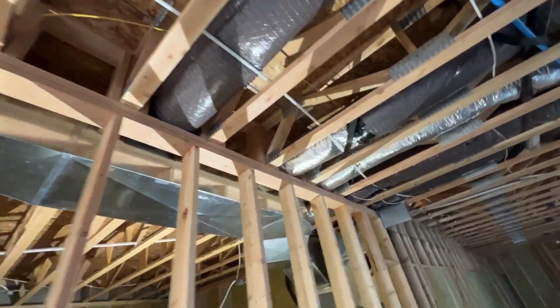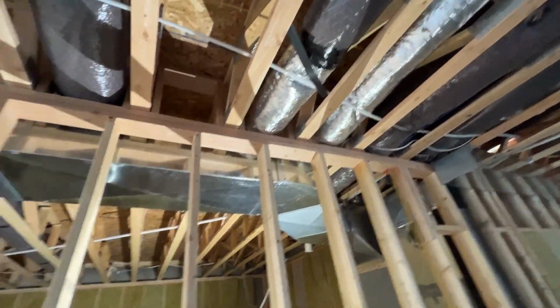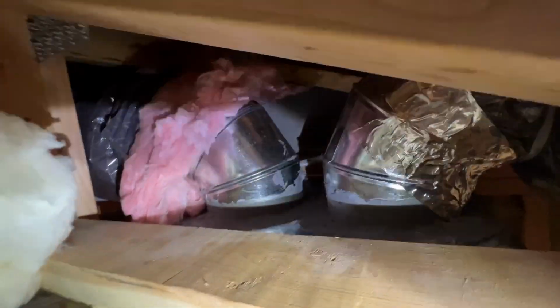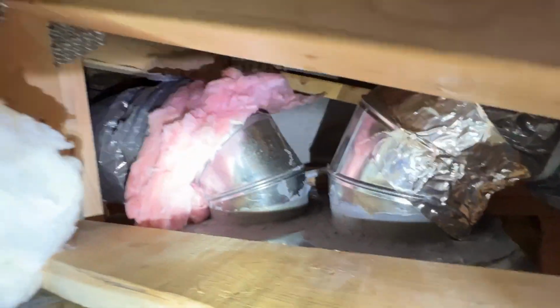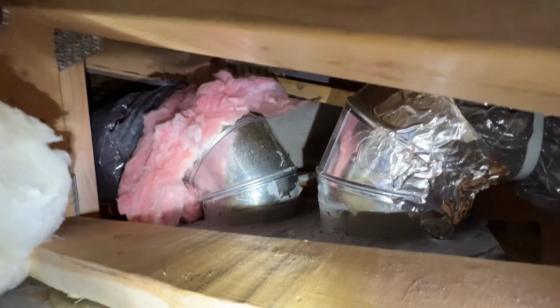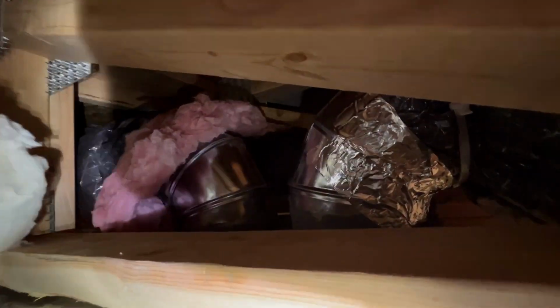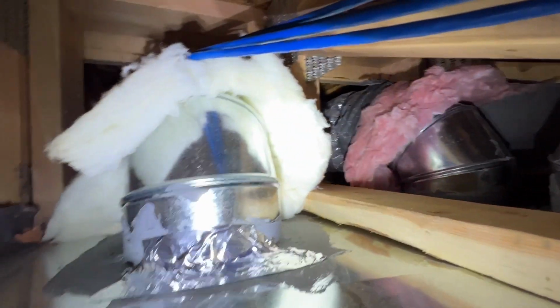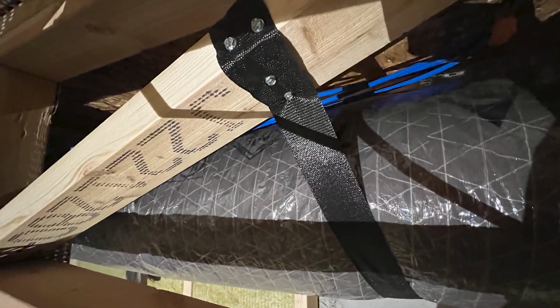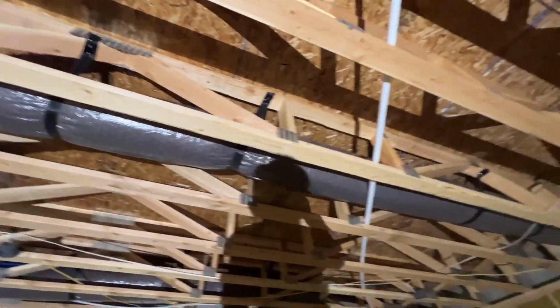On the outside, we've got several supply lines shooting down and over into the top, and up here you can see how it connects to the top of the trunk line. We still need to shove in insulation and get things taped up, but that's how it connects through those elbows drilled in through a hole at the top. That gives it a really clean look and keeps it all up in the ceiling. We used straps to help keep the flex duct level and prevent it from sagging.